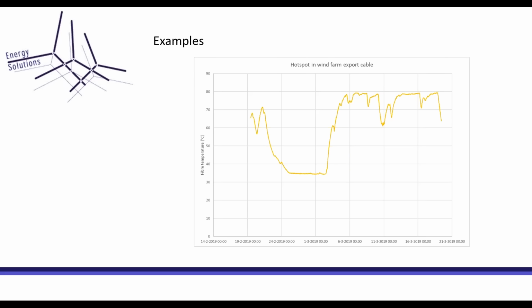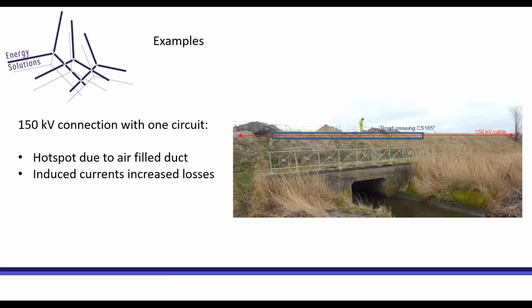So this was a very good example of how dynamic cable rating or real-time thermal rating prevented a failure in the power cables. The last example I wanted to show is a 150 kV connection from a TSO with only one circuit, where also indirectly a lot of offshore wind was connected. There was a problem, also a thermal problem, only on a small section of about 10 meters, which was not understood fully.